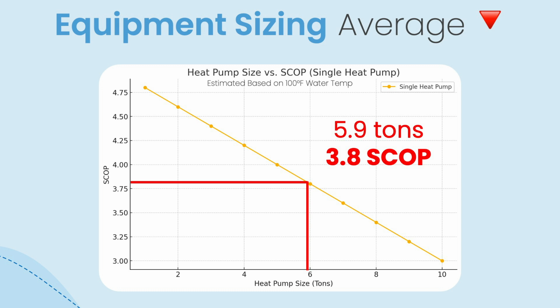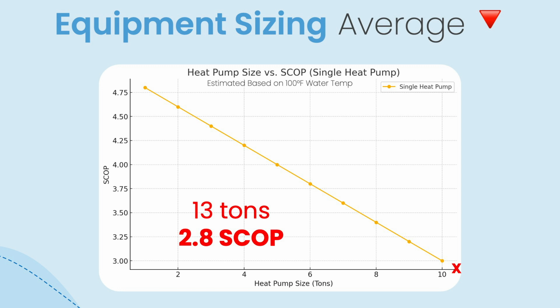We'll go more into that in a second, but just to use this, first of all, if we plot our average designer's heat pump on here, so 5.9 tons is what he thinks it's going to be at. That intersects with the line there, and as we go across, it achieves a 3.8 SCOP. Not bad at all. So that would be turning every kilowatt into 3.8 of heat output, which is pretty good. It's definitely not terrible. Problem is, he didn't do the heat load calcs properly as we went through. So his performance is off the chart in this one in a bad way. He might not even do 2.8.